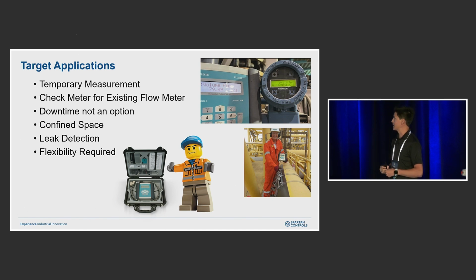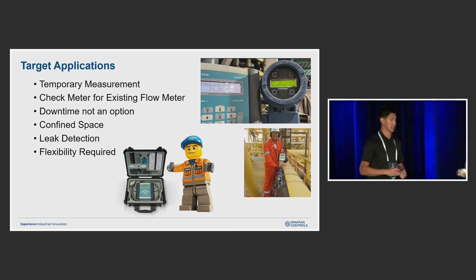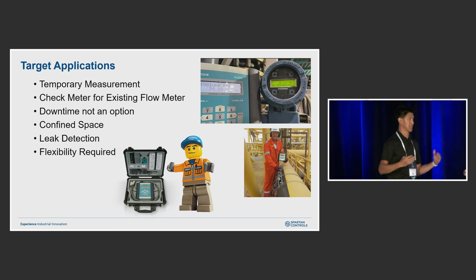Or if we have a situation where downtime is just not an option, we can quickly throw a meter on there. The picture on the bottom right is an example of where a flow meter had delivery delays. Not that we have ever heard of that in the last 5 years. But we can quickly throw one of these on, get a flow measurement until that more permanent measurement shows up. Another one that we've run into recently is if you have confined space locations or an old flow meter, then it becomes very cost prohibitive to take that mag meter out of line. We can put one on quite easily onto that line.